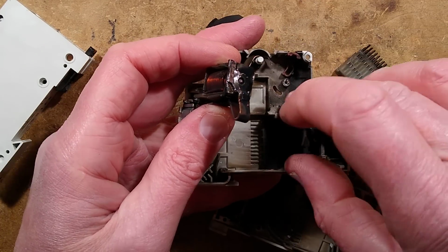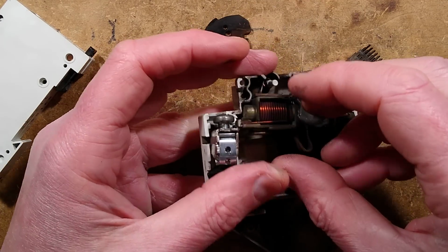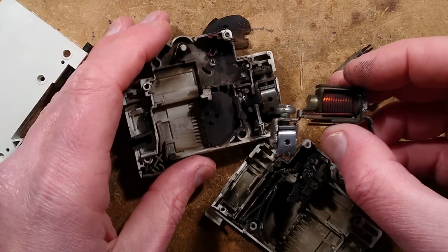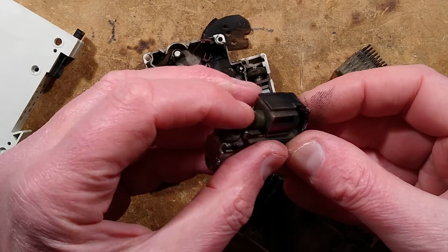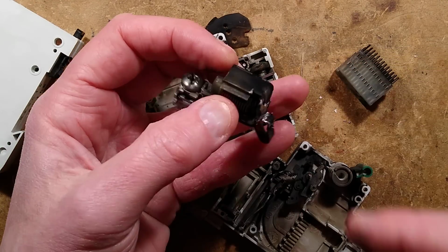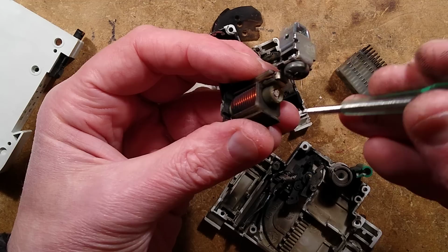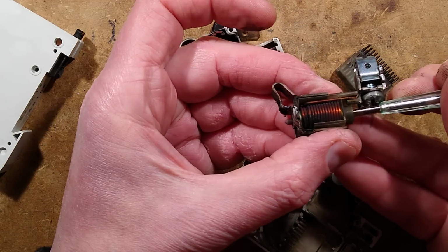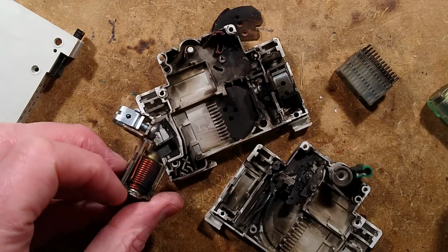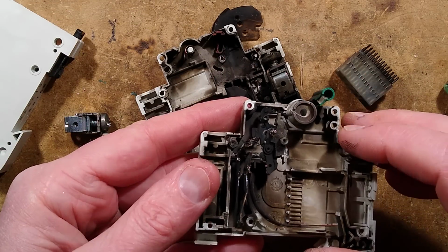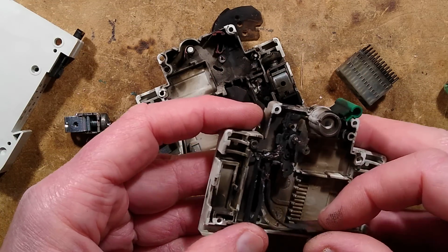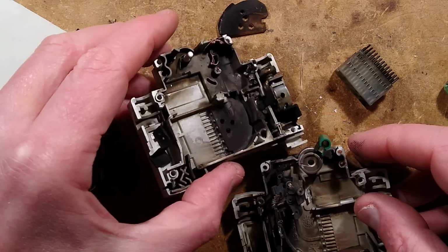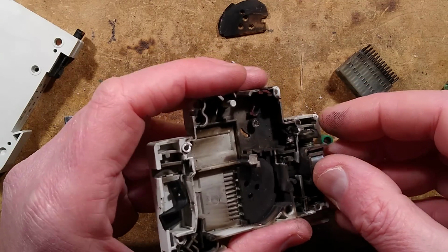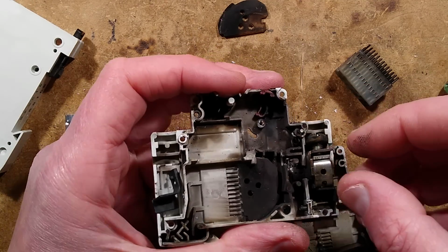Has the contact absolutely vaporized inside completely? Here's the solenoid mechanism designed to trip in the event of an overcurrent situation like this. The little plunger should go down, and it still can. But ultimately I don't see much left of the contact. I think it's been obliterated. We can find this out though. There's a melted spring in here.